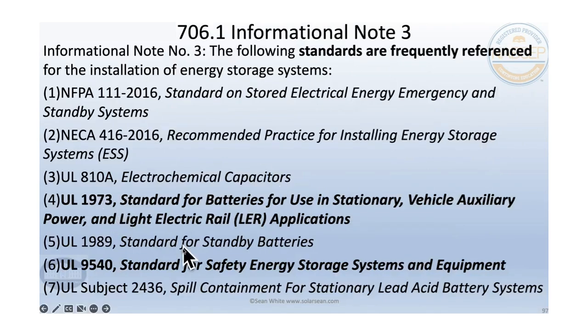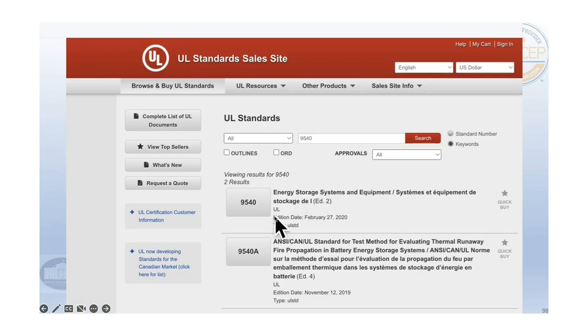So what we're looking for is 9540. Pretty much all of our 9540 energy storage systems have 1973 batteries, and that would cover the lithium-ion batteries. So just by being 9540, it means that it's also 1973, unless somebody comes up with a lead-acid one, and then it would be using this one at the bottom, number 7. And so here's 9540. You can go read that for free at the UL website. You just have to put in a lot of passwords and things like that.